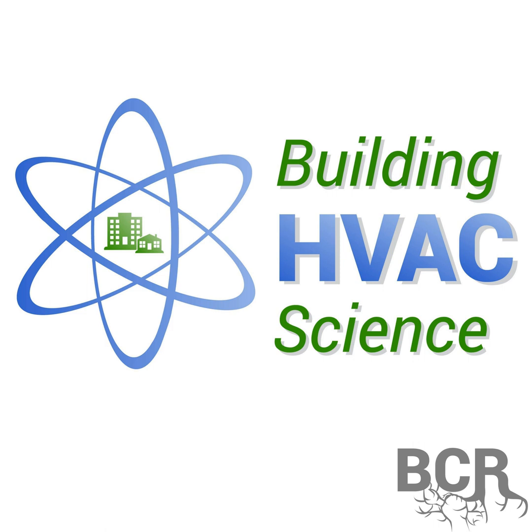So the conventional wisdom is that individual room returns are the gold standard for room pressure balancing. And we find with the systems that we're designing, it's completely unnecessary most of the time to have individual bedroom returns, because our systems are as right sized as we can make them. We're not delivering massive amounts of air to the bedrooms. And through our testing, we are proving that even with the doors closed, we're not getting any more than a 4 or 5% reduction in airflow. That's kind of the worst case. At 3 pascals, you get about a 5% reduction in airflow, and that's something we're definitely willing to live with.